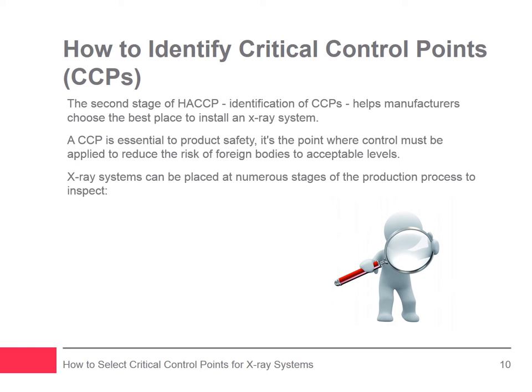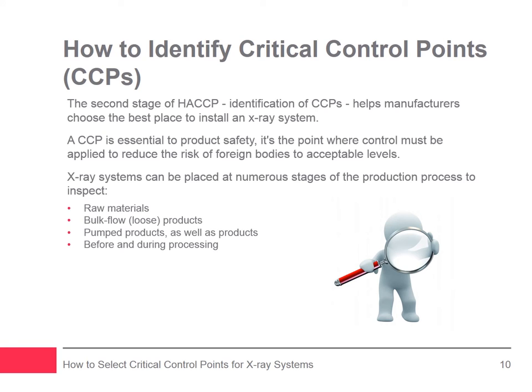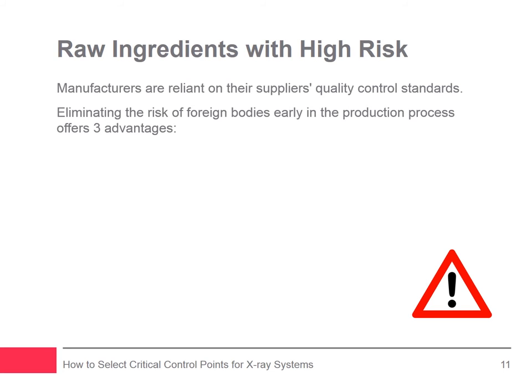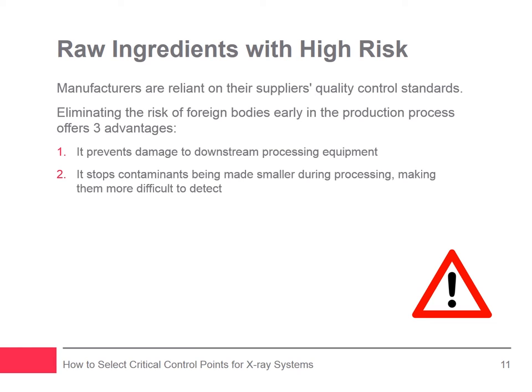X-ray inspection will be most effective at detecting foreign bodies at the following stages of the production line: inspecting raw materials, bulk flow, loose products, pumped products, products before and during processing, after processing, before packaging and sealing, after packaging and sealing, and final cases. Raw ingredients come with a high risk of foreign bodies, and manufacturers are reliant on the quality control standards of their suppliers. Some manufacturers insist that their suppliers have x-ray systems installed. An undetected stone or shard of metal can cause damage to downstream processing equipment or be made smaller, making detection more difficult. Early detection keeps costs down by eliminating contaminants before value is added through processing and packaging.